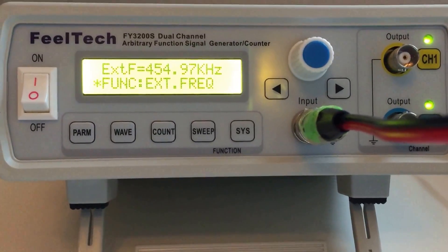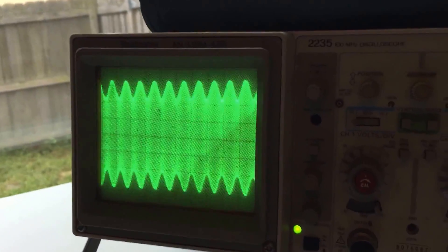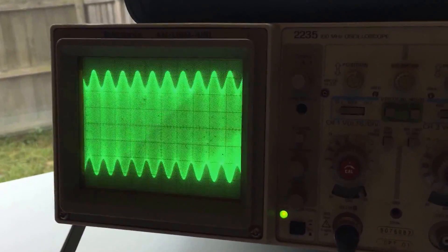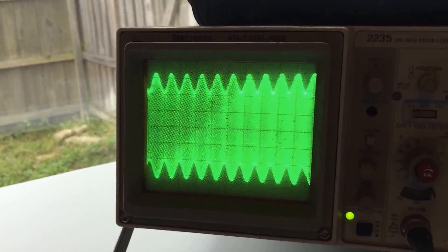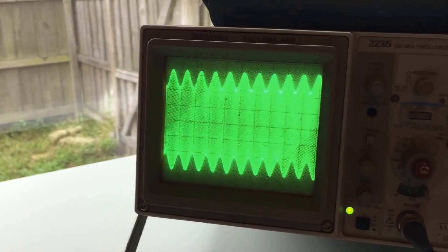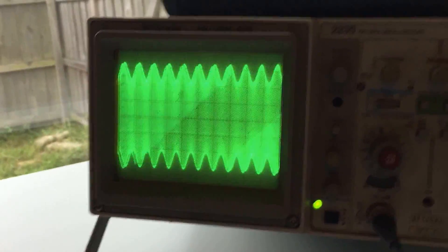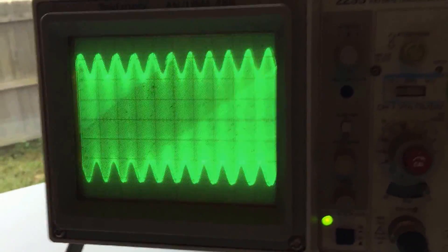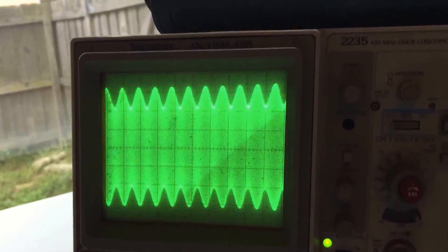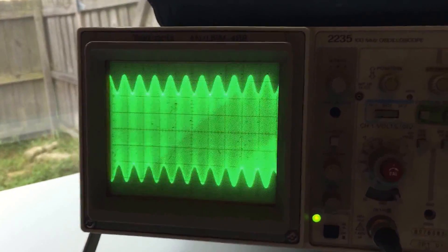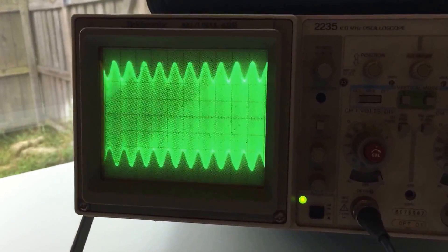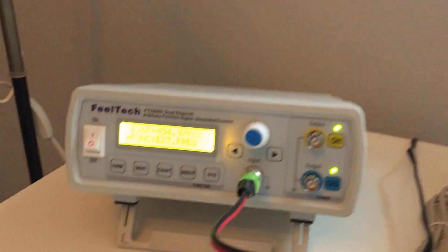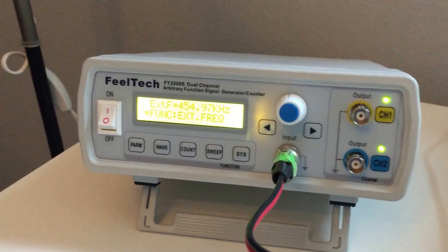And the book says that it requires a minimum of 2 volts. I found that it will still work at 1.5 volts. What we're looking at now is 1.5 volts. For the waveform to come up. I had it much lower than that, and it didn't register anything at all on the box. It just showed zero.